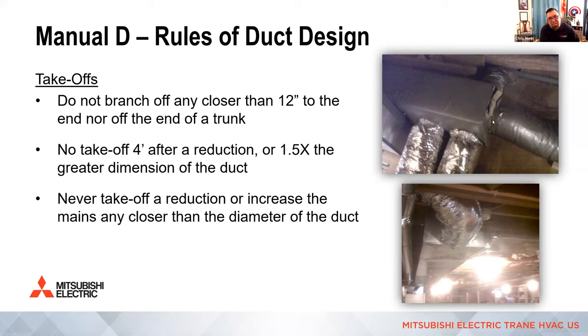This is a tough one. The second one down is really hard to abide by. And I put this in here just so that you guys can give it as much space as possible. You don't want to have a takeoff within 4 feet of a reduction of a trunk, or 1.5 times the greater dimension of the trunk, right? So if it's 20 inch wide, you don't want to be within 30 inches of that. This is really hard to do residentially. The key here is just stay as far away from a reduction in the trunk as possible so you don't depressurize it like the end cap example.